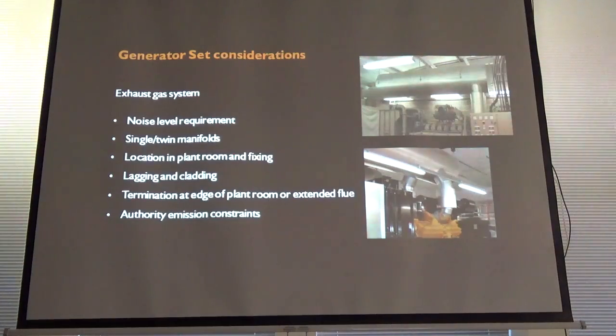And that's related to the discharge velocity as well, because often with flue systems what we'll do, we'll work within the pressure constraints, we'll actually throttle it down the last couple of metres to actually make sure it's banging out at sufficient velocity to clear the building. Because if it's just dropping out of the actual flue itself, it can accumulate on a building where a lot of people like the sky gardens and things like that, you can get a build-up of the emissions, which causes respiratory problems.